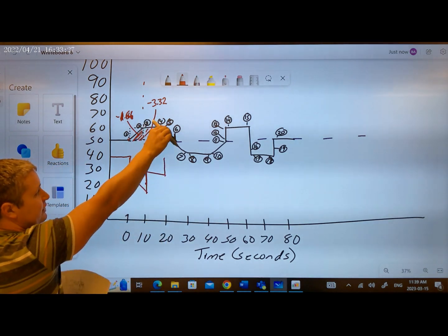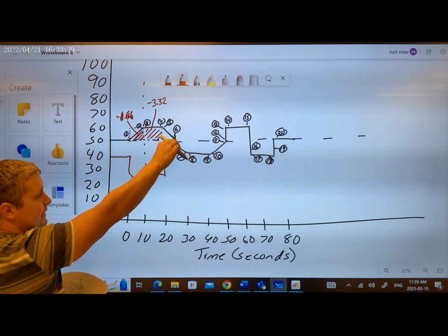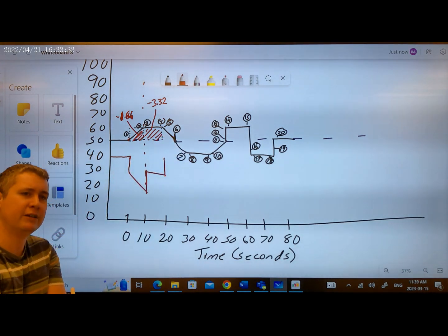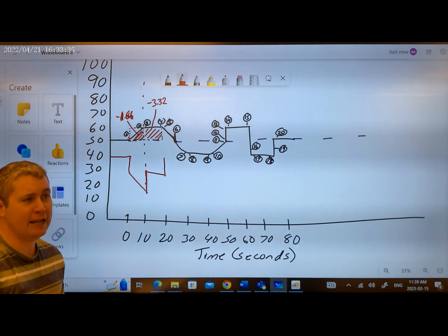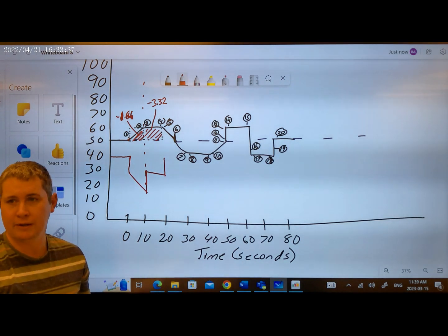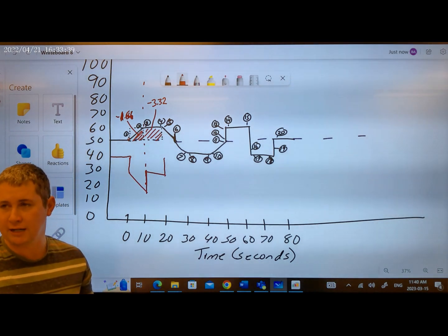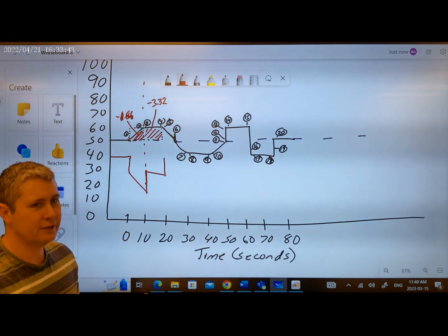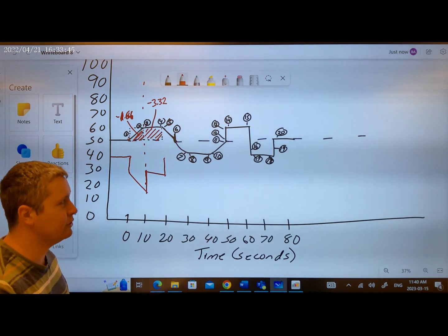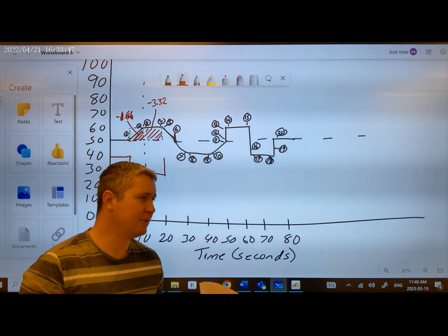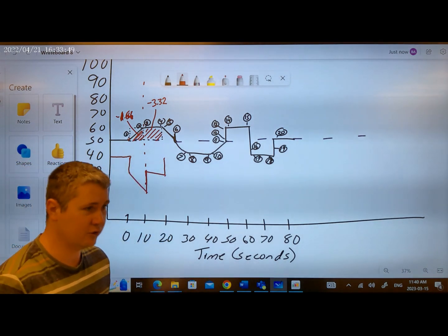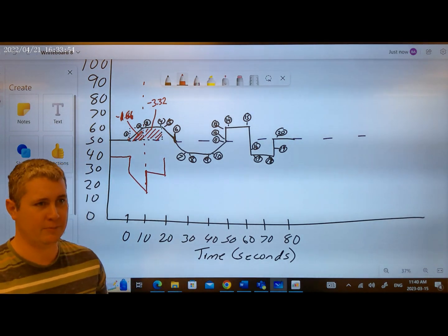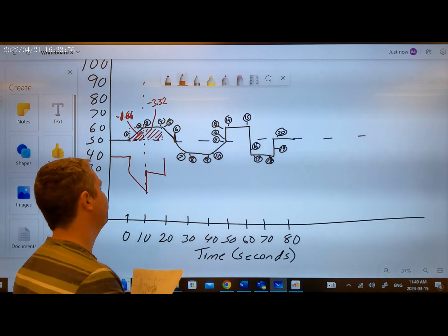So as soon as we started to come on this ramp rate coming down, we jumped in a positive direction because derivative does not like change. When there is change, derivative is trying to compensate so that there is no change. Now, obviously, we want change in controllers, but the purpose of derivative is so that you don't overshoot. You don't get too much of a ramp rate. It wants to slow down that ramp rate. It wants to slow down the change.